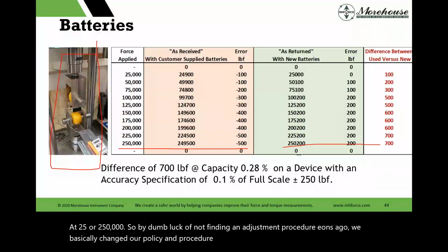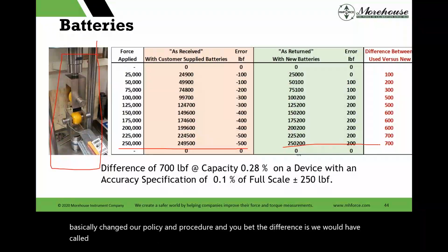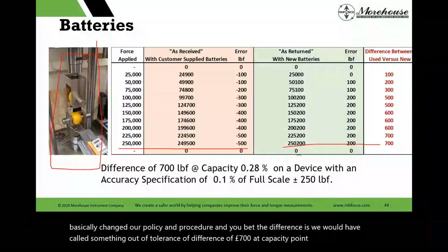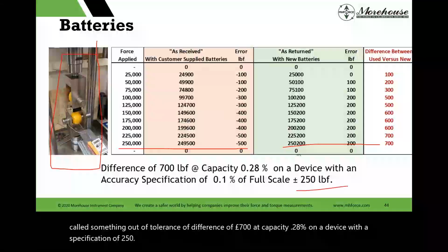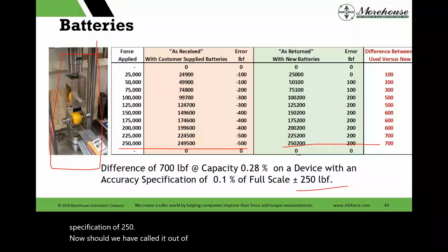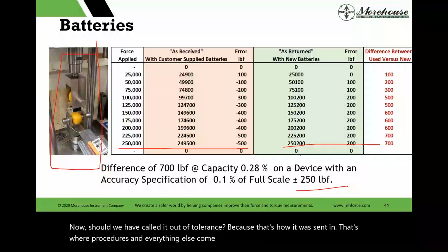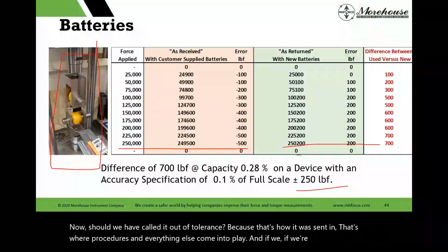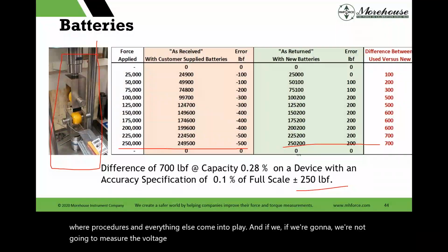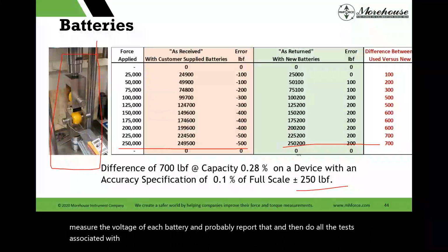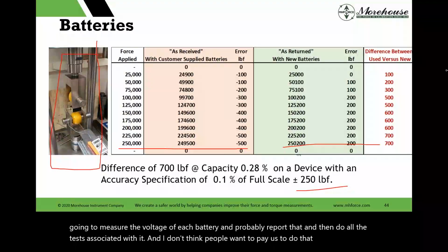And you bet the difference is we would have called something out of tolerance, a difference of 700 pounds at capacity, 0.28% on a device with a specification of 250. Now, should we have called it out of tolerance because that's how it was sent in? That's where procedures and everything else come into play. And we're not going to measure the voltage of each battery and probably report that and then do all the tests associated with it. And I don't think people want to pay us to do that. So the policy is basically to put in new batteries.